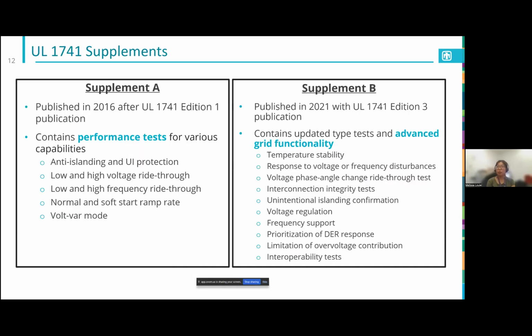So UL 1741 also contains supplements that are continually updated over time, including the two that are shown here. Supplement A was published in 2016 after the publication of edition 1 of UL 1741. It contains performance tests for capabilities including anti-islanding or unintentional islanding protection, voltage and frequency ride-through requirements, ramp rate requirements, and volt-var mode requirements. And the more updated Supplement B was published in 2021 with the publication of edition 3 of UL 1741. This more recent certification has updated type tests as well as advanced grid functionality requirements that were not contained in Supplement A.